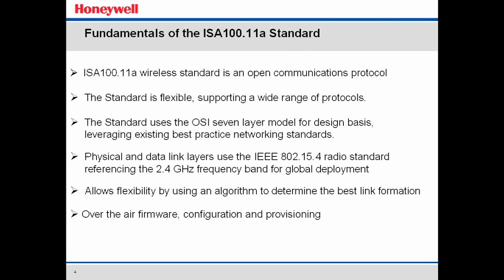What that means is once the transmitter is installed in the field, you're not going back to it to do anything except once every 3 to 5 years to change batteries. All of the configuration, all of the security, all of the firmware, everything is done over the air.